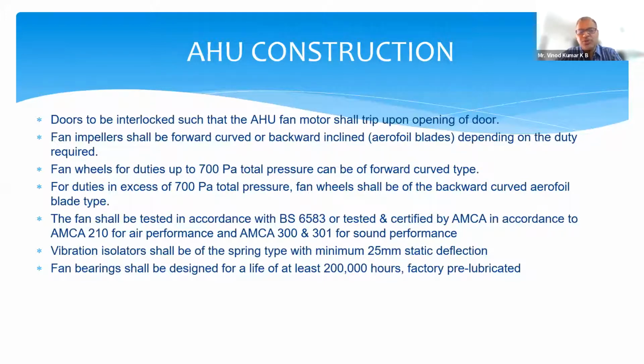Now, coming to the most important part of the AHU, the fan. There are various kinds of fans. Many people, when they select the AHUs, select the lower-cost fans. Is it the right fan? It may not be. Why? Because there are two kinds of fans or impellers, the forward curve and the backward curve. Forward curved fans are selected for AHUs when the total pressure is below 700 pascals.